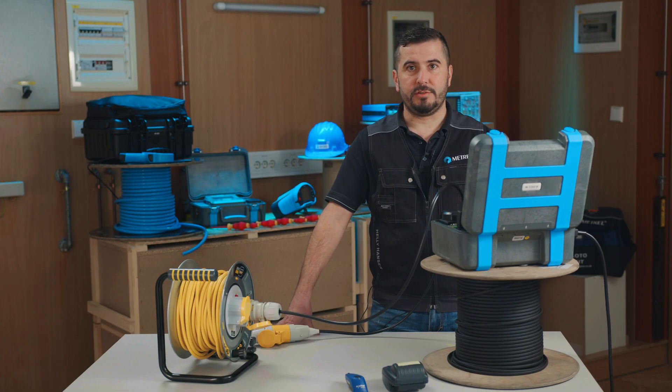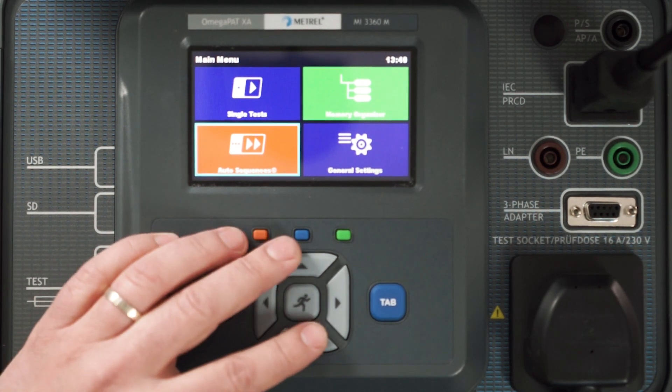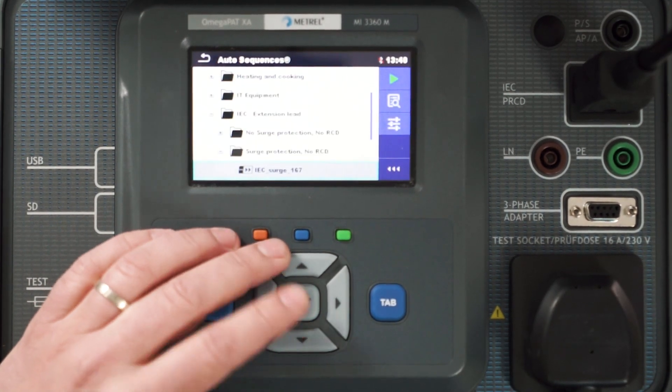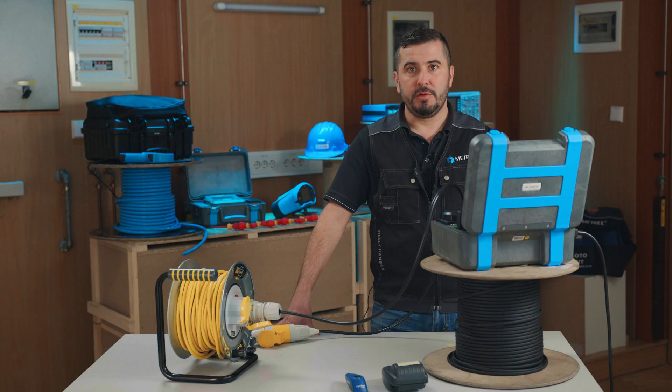First we enter the auto sequence menu and choose the correct test sequence. We will select it from the group General, which is designed based on the information provided in the 5th edition Code of Practice for in-service inspection and testing of electrical equipment. Inside, we search for the group IEC extension leads, from where we will select a test sequence dedicated to extension leads with long cords and no additional RCD protection.